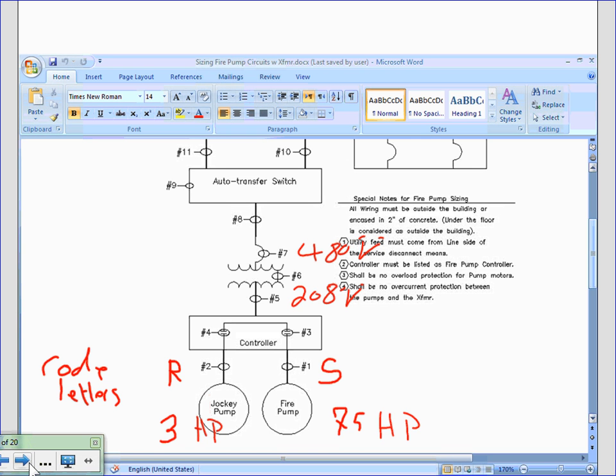Could it happen? Yes. Is it a good idea? No. If you have a 480, run them at 480. The only thing I can think of is you probably have a good deal on a fire pump controller in your building, or the mechanical engineers specify them for whatever reason to run at 208, and I have a 480 system. So what do we do?